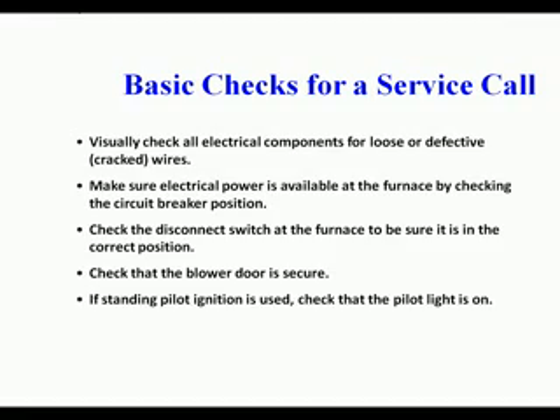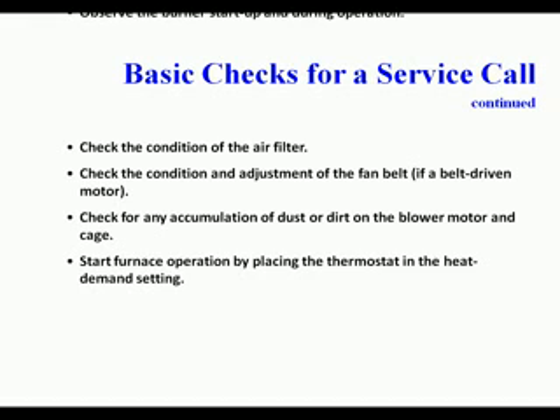You want to visually check all electrical components for loose or defective wires. Make sure electrical power is available at the furnace by checking the circuit breaker position. Check the disconnect switch at the furnace to be sure it is in the correct position. Check that the blower door is secure, and if standing ignition is used, check that the pilot light is on. Check the condition of the air filter. Check the condition and adjustments of the fan belt. Check for any accumulation of dust or dirt on the blower motor and cage.